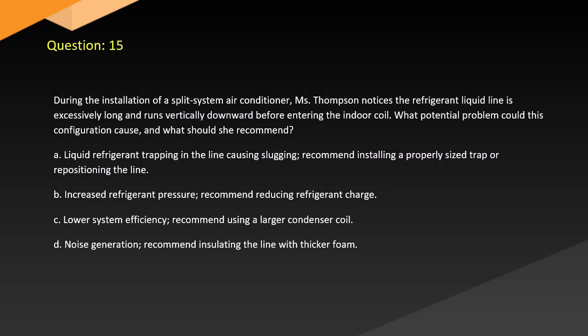Question 15. During the installation of a split-system air conditioner, Thompson notices the refrigerant liquid line is excessively long and runs vertically downward before entering the indoor coil. What potential problem could this configuration cause, and what should she recommend? A. Liquid refrigerant trapping in the line causing slugging. Recommend installing a properly sized trap or repositioning the line. B. Increased refrigerant pressure. Recommend reducing refrigerant charge. C. Lower system efficiency. Recommend using a larger condenser coil. D. Noise generation. Recommend insulating the line with thicker foam.